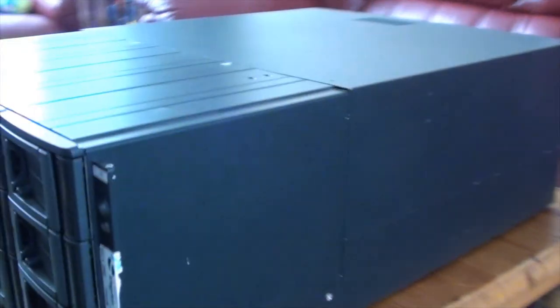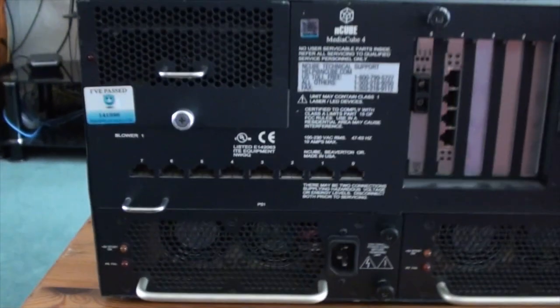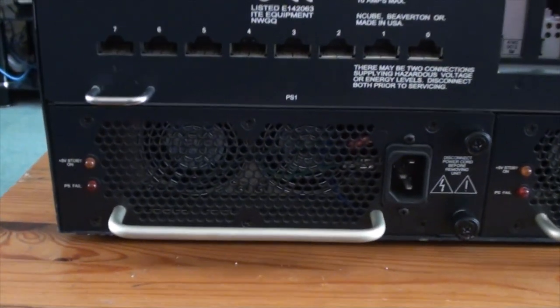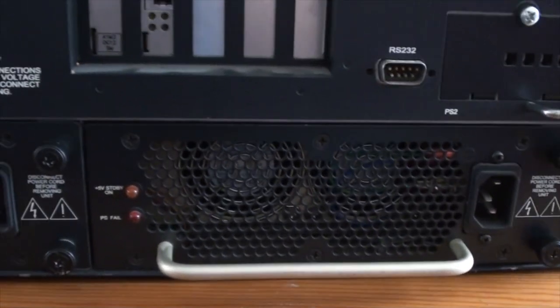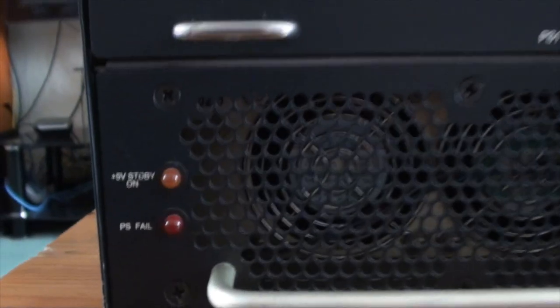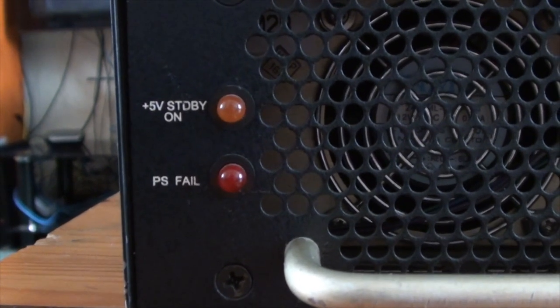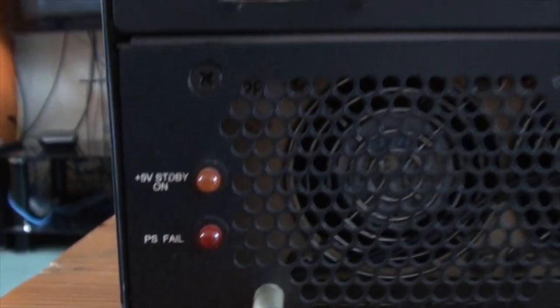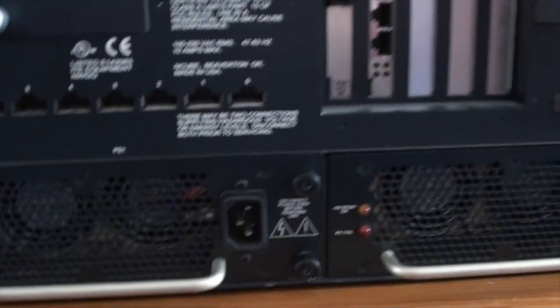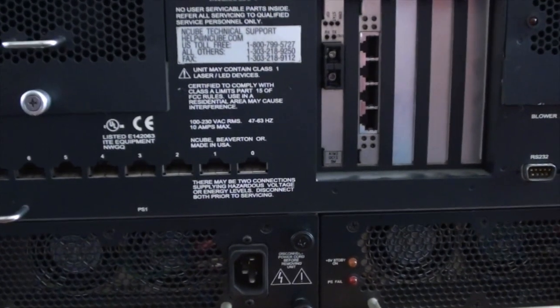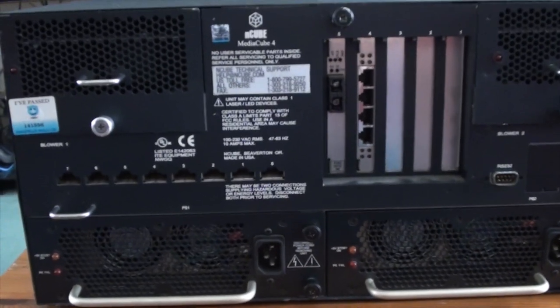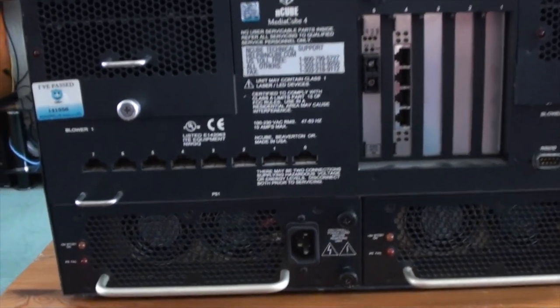Now, if we go round to the back, what we find here is we've got two power supplies. We've got one on the left, one on the right. Both of those are redundant power supplies, so that's why you've got a little LED on each of them which says PS fail for power supply failure. So if one power supply fails, the system will still run, the indicator LED will light up, so the system administrator can replace the power supply.